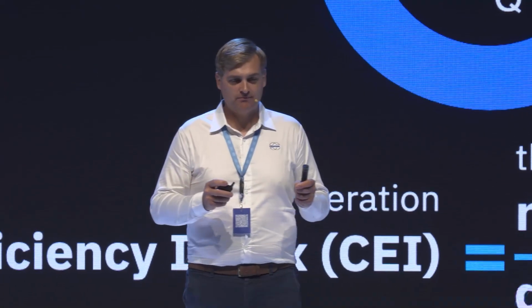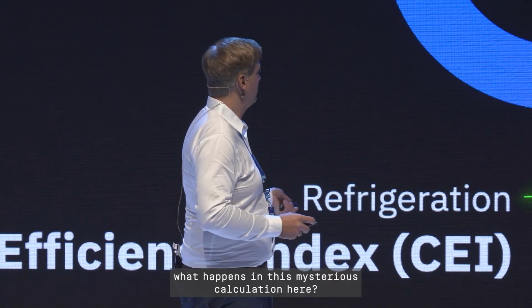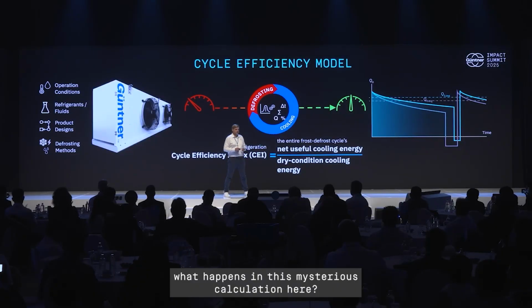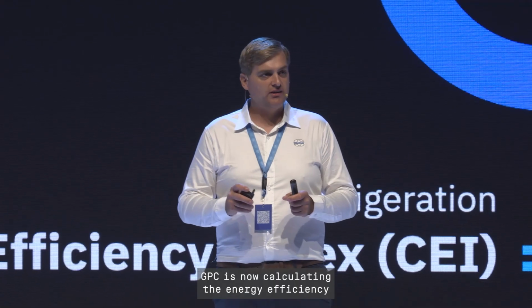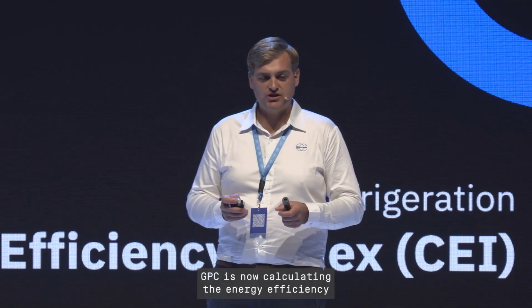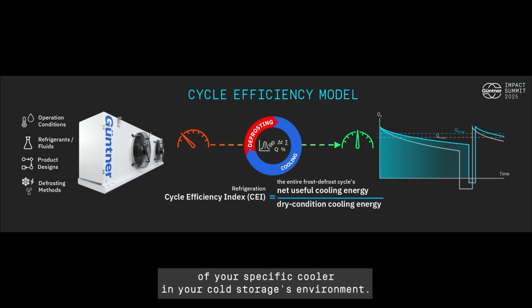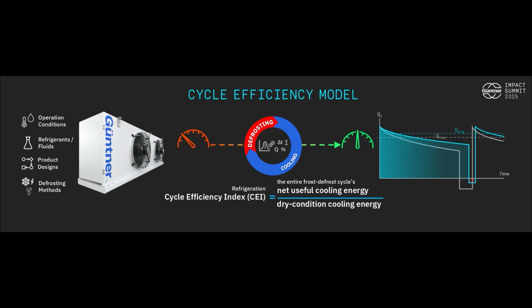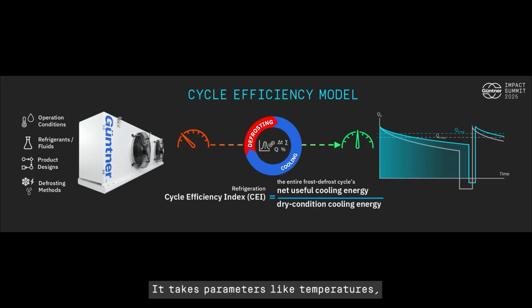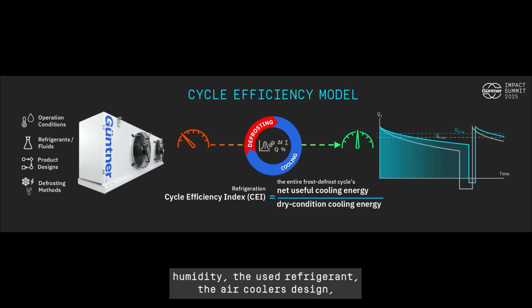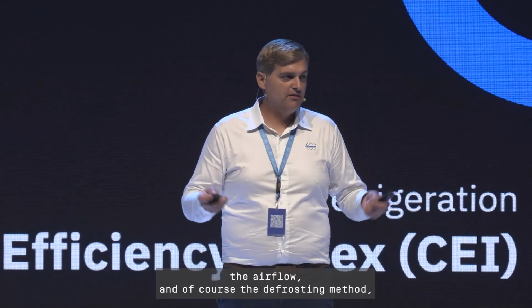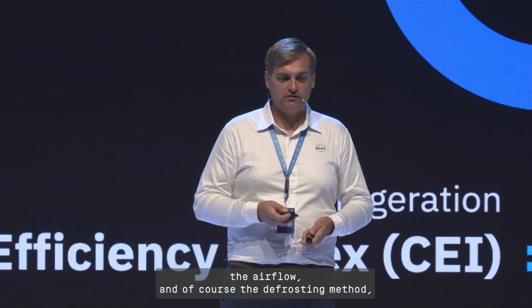In a nutshell, what happens in this mysterious calculation? GPC is now calculating the energy efficiency of your specific cooler in your cold storage environment. It takes parameters like temperatures, humidity, the used refrigerant, the air cooler's design, design parameters like fin material or spacing, the airflow, and of course the defrosting method.